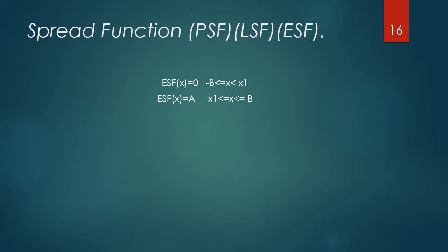It can be seen that the ESF can be easily obtained experimentally due to the simple form of the plate required for the experiment we named before. Once the image has been obtained with the system, a cut is made perpendicular to the edge, obtaining the ESF. To calculate the LSF of the system, the ESF must be differentiated.